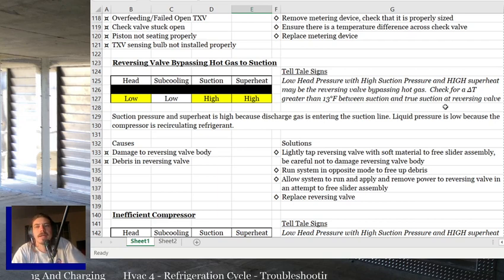So the causes are damage to the reversing valve body or debris in the reversing valve. Solutions: you can lightly tap the reversing valve with a soft material to free up the slider assembly, like a soft mallet or another piece of copper covered in a cloth, whatever. You want to tap the slider assembly in the reversing valve, but you don't want to dent the reversing valve, because if it wasn't sticking, it'll be sticking after you put a dent in it. Be careful not to damage the reversing valve body.